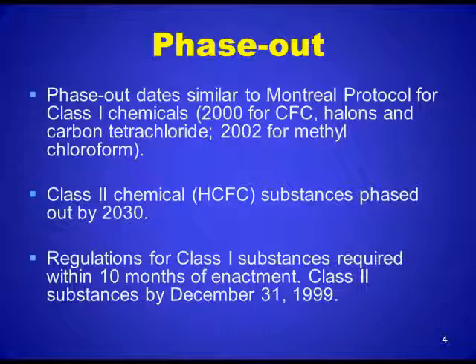Class II chemical substances had to be phased out by 2030. Regulations for Class I substances were required within 10 months of enactment. Class II substances had to be regulated by December 31, 1999. The 1990 Amendments also required EPA to publish a list of unsafe substitutes for Class I and Class II chemicals and to ban the use of unsafe substitutes.